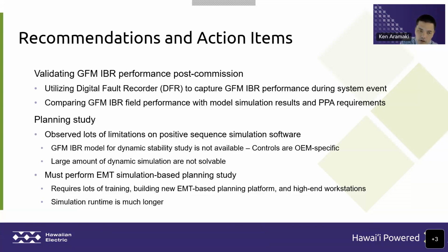So that's why we used PSSE as a screening tool to see where the risk events are, and then we used the EMT simulation to look at those high risk scenarios. This is because EMT simulation takes much more time to do versus a positive sequence simulation. And going forward, we have to continue to grow our internal resources to be able to execute these EMT simulations. That's going to require much more training, better software, and also higher end workstations.